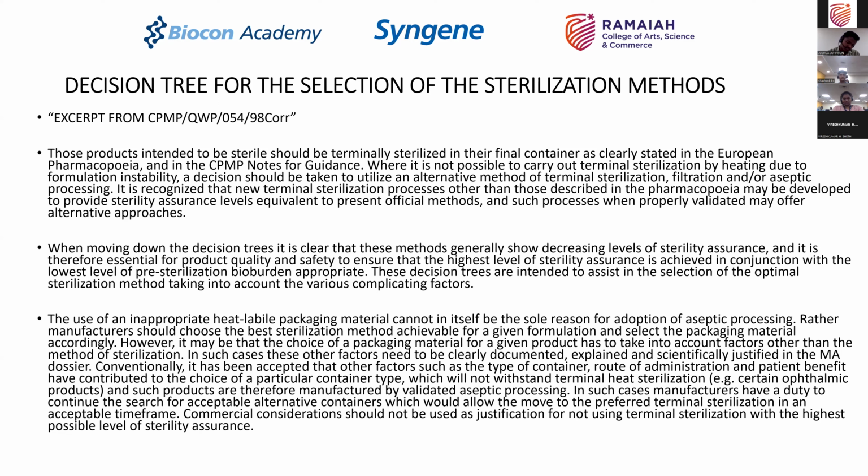Okay. Now, the use of inappropriate heat labile packaging material cannot in itself be a sole reason for adoption of aseptic processing. Rather, manufacturers should choose the best sterilization method achievable for a given formulation and select the packaging material accordingly.